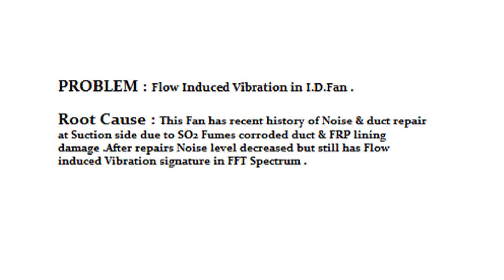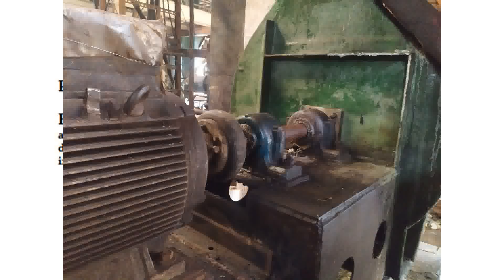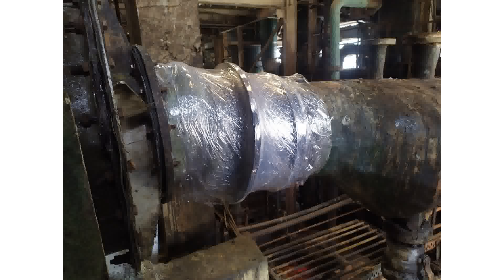This fan recently developed a huge noise. After inspection, they found that the suction area duct had been corroded by sulfur fumes. After that, they changed the duct and carried out repair works as well. The noise decreased somewhat, but some noise was still present.